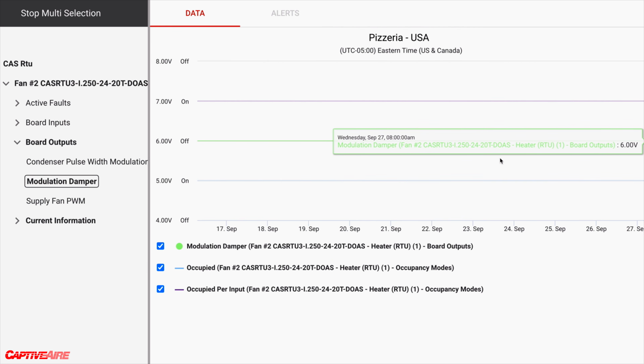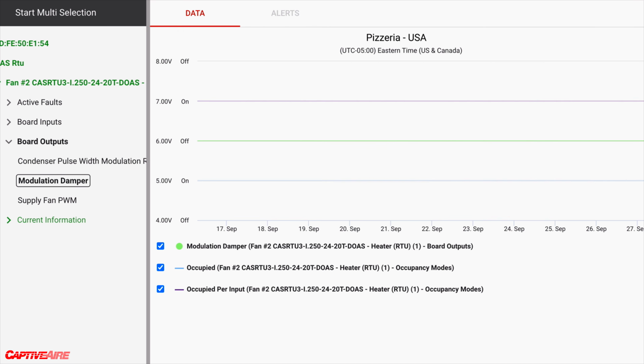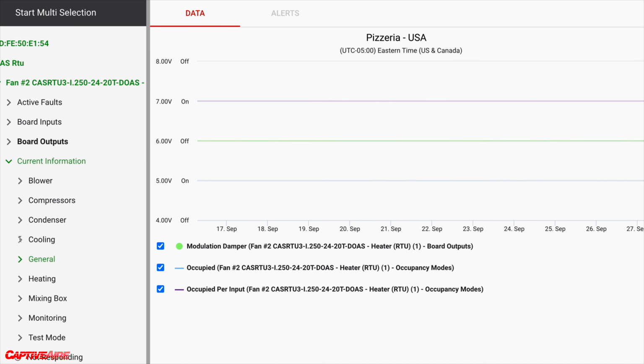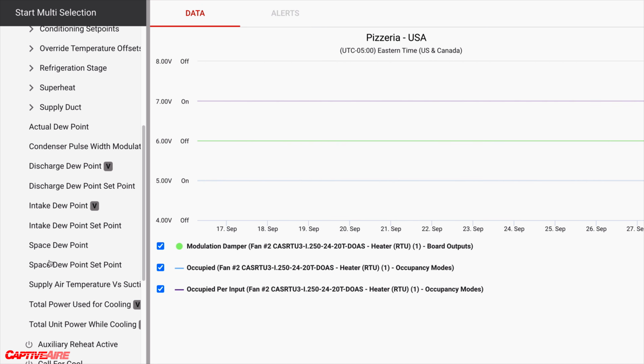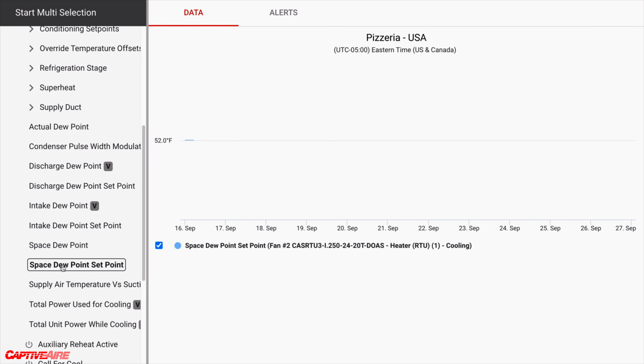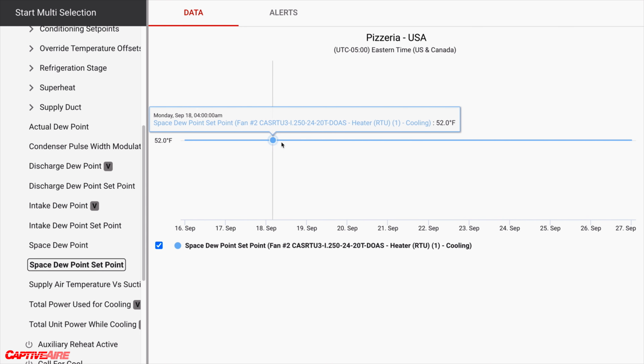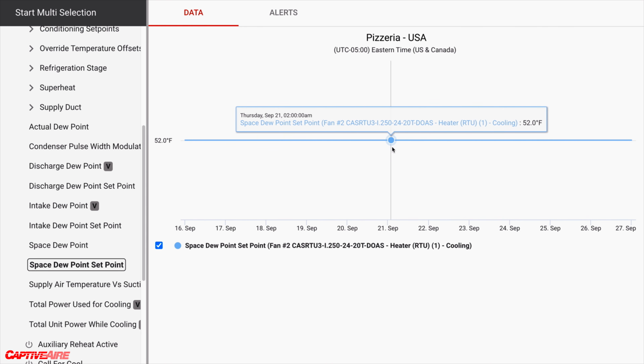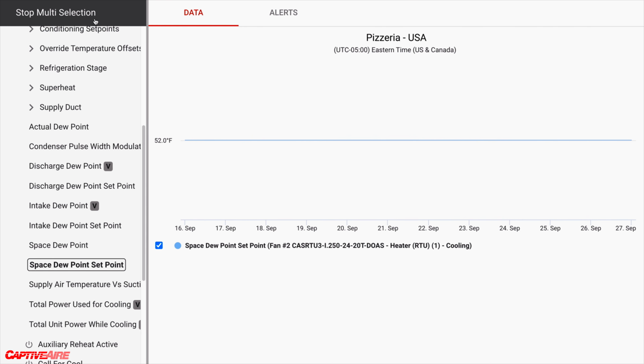But the other thing I'm curious about is during the audit, it was noted that we were running with too aggressive of a dehumidification set point, and we were actually overshooting our humidity set points. And I'm going to change off the occupancy here. More what I want to get into now is focusing on the comfort and the humidity of that space. So I want to see during our occupied times, what's our space dew point set point? So we're targeting a 52 dew point in the space. And then I want to see what the actual space dew point is reading.